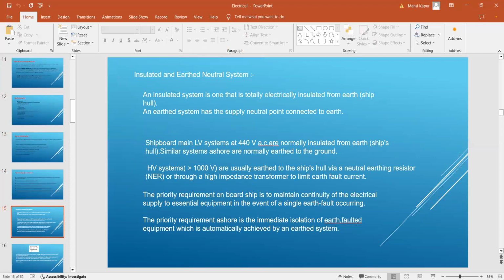So an insulated system is one that is totally electrically insulated from the earth. So what does it mean? Suppose this is your generator and this is the neutral point, right? And this neutral point is not earthed anywhere. This is known as insulated. So you have kept the earth as insulated. What is neutral earth? This is the point you are going to ground.